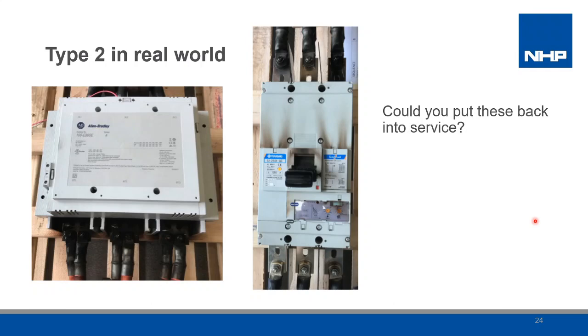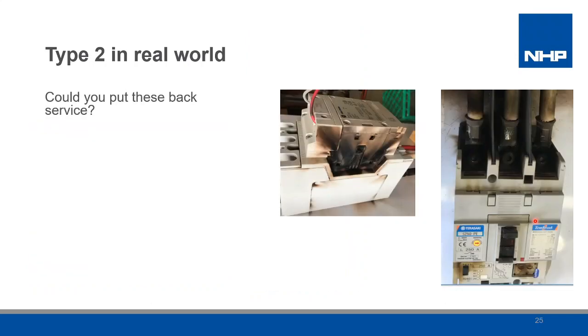If we look at the MCCB and contactor which passed in the first test video, there are sooting marks on both devices where arcing has been vented. These components are suitable for continuous service, but maintenance inspection of the MCC cell should be undertaken to ensure the vented gases and material have not caused insulation degradation elsewhere. The MCCB and contactor here have seen a short circuit fault, but when these starters are installed at a customer site, from the testing they can be placed back into service.